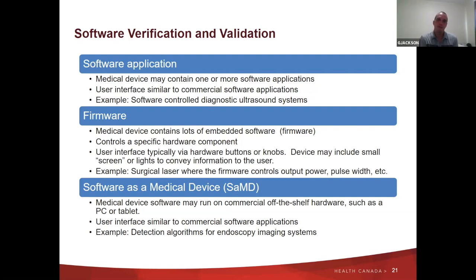And we have some things called software as a medical device, where the whole device is a separate software. We've seen, say, detection algorithms for endoscopy imaging systems. It's a separately licensed device, compatible with specific systems and requires their images to run, but it's licensed by itself as its own device in that case.